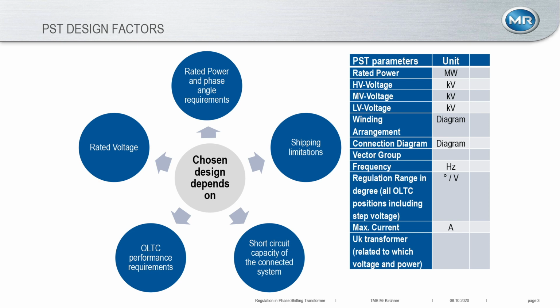This is different with phase-shifting transformers. If we look at phase-shifting transformers, a limited component in many cases can be the on-load tap changer. And if this is the case, you have to start with the ability of the on-load tap changer and then adapt your transformer design to be able to get out most of what you need from your phase-shifting transformer. So it can happen that you have to change your design based on the on-load tap changer. And another important thing is the short circuit capacity of the connected system.